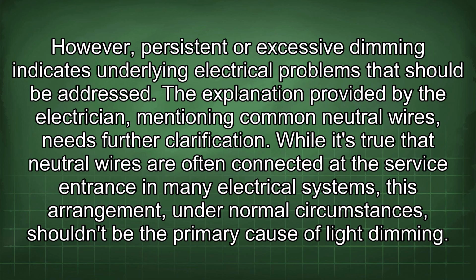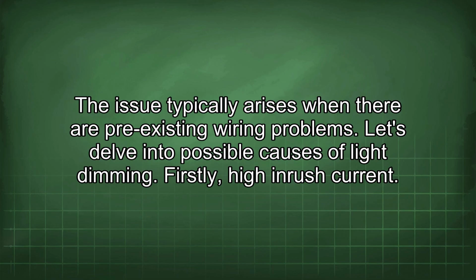The explanation provided by the electrician, mentioning common neutral wires, needs further clarification. While it's true that neutral wires are often connected at the service entrance in many electrical systems, this arrangement, under normal circumstances, shouldn't be the primary cause of light dimming. The issue typically arises when there are pre-existing wiring problems. Let's delve into possible causes of light dimming.